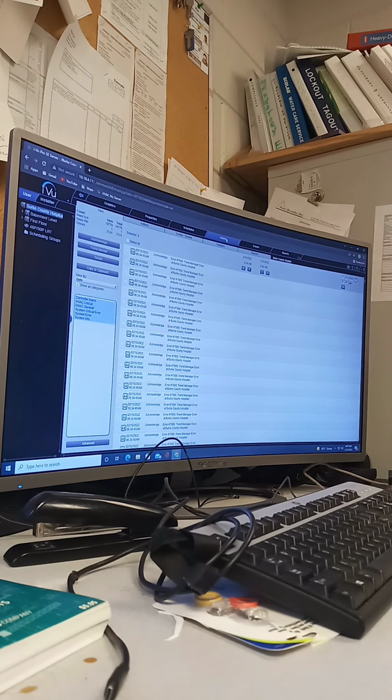Okay. How I like to do alarms, notice we got a lot of trend errors. I'm going to have to go in here. It's looking for data that's not there. So I need to go in there and fix that so we're not getting all these bogus alarms right there. It's looking for a piece of data to try to trend that's not there. So it's saying, hey, I can't see it. I'm going to show you an alarm. So we'll fix that. Okay.